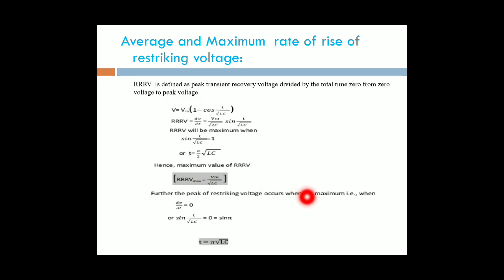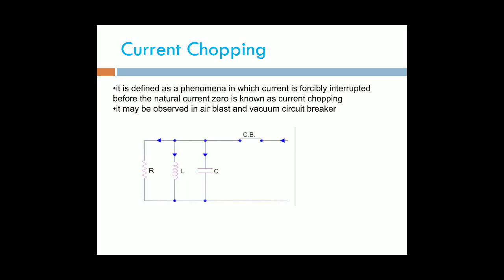Further, the peak of the restriking voltage occurs when V is maximum. V is maximum means sin t by root LC equal to 0. Therefore, dV by dt equal to 0. This is the average and maximum values of RRRV, or rate of rise of restriking voltage.